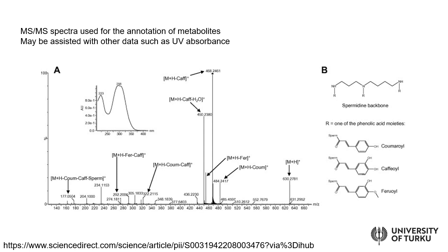On the other hand, if you use the data independent approach, you will be able to catch the fragmentation information of all the signals. So if we say that this is a full scan analysis, all these signals would go to the MSMS fragmentation, and you produce a huge amount of fragmentation information in one go. So there you gain much more information, but on the other hand, you also produce a challenge for yourself on the data analytical side, that how can I match these? So it's a little bit of balancing that.